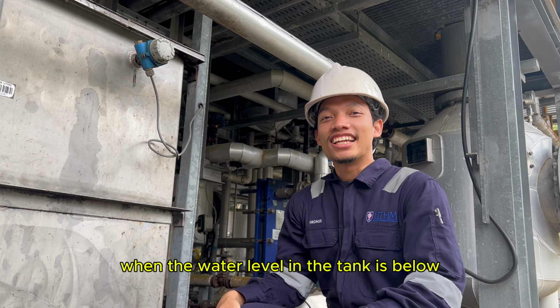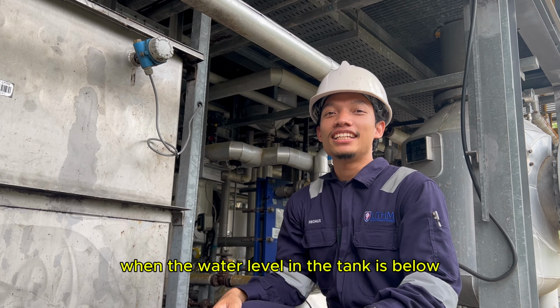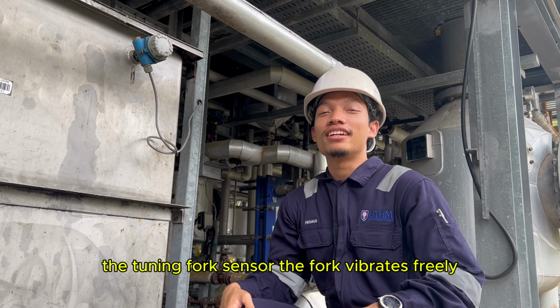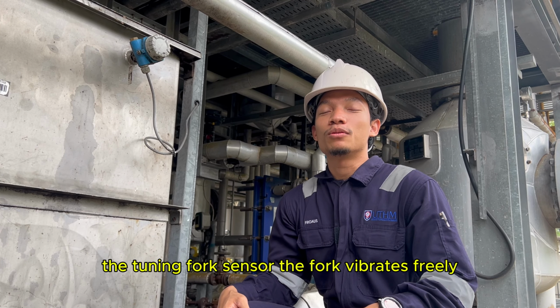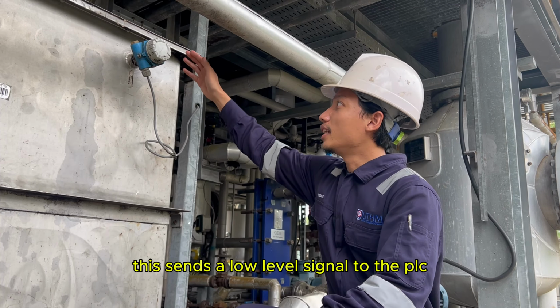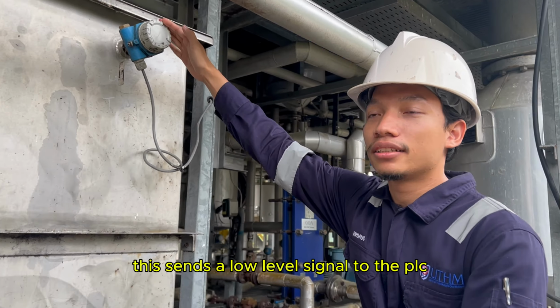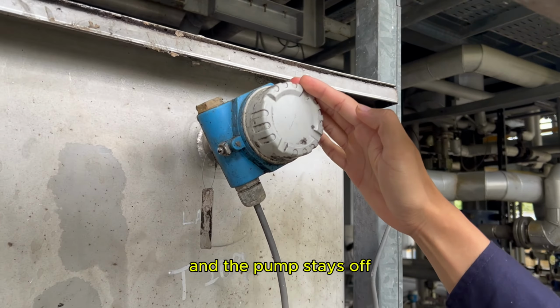Here's how the system works. When the water level in the tank is below the tuning fork sensor, the fork vibrates freely. This sends a low level signal to the PLC and the pump stays off.